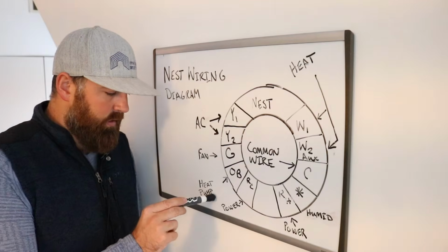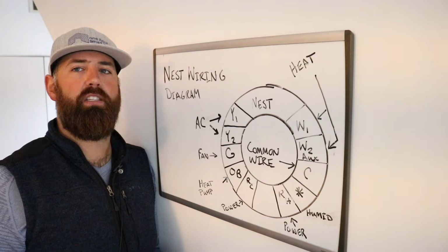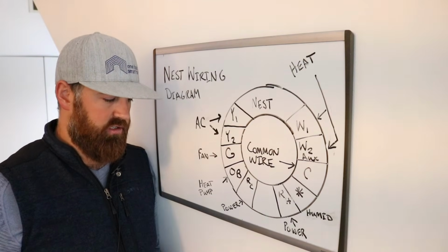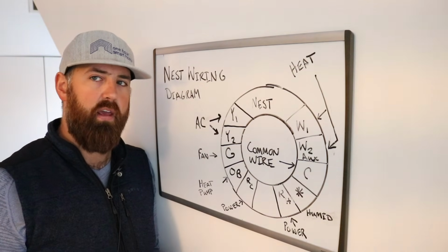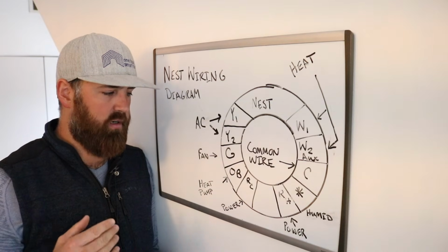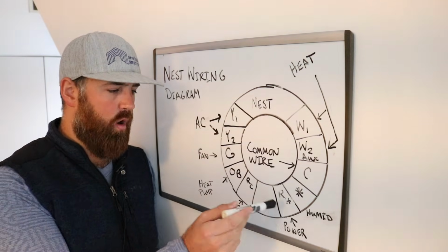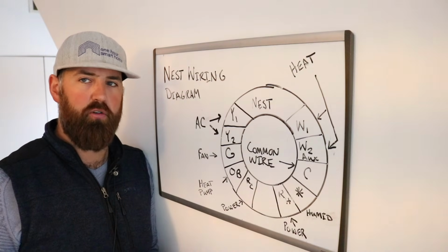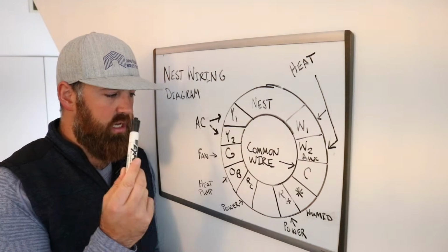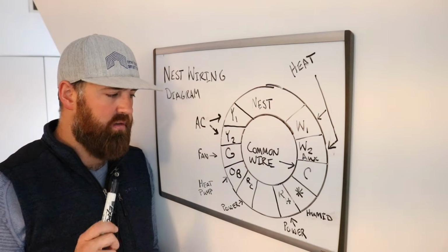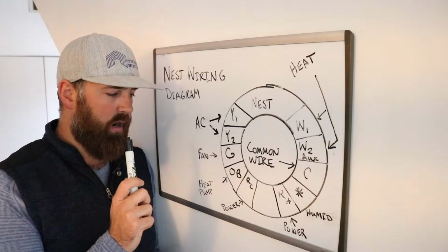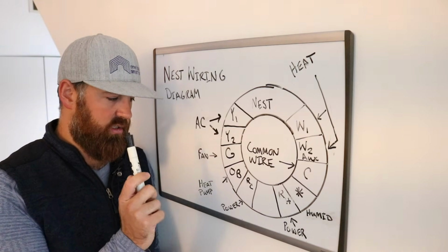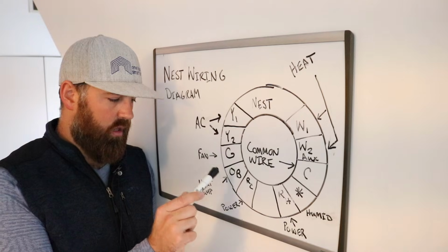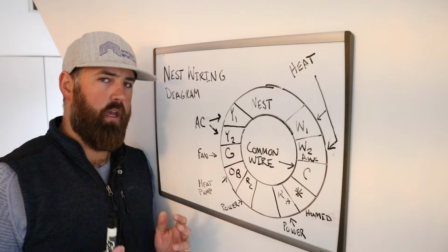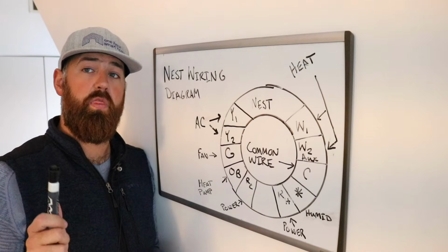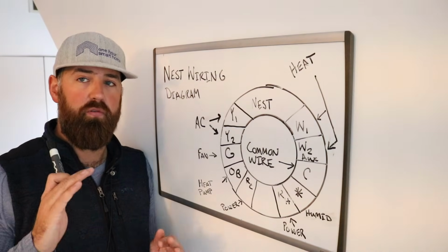The next one is the RC, and RC and RH are related - they are both power. When we talked earlier about how a thermostat and HVAC system work, RC and RH basically do the same thing for the most part in most systems. RC is power and RH is power. For most of you, you could hook up your red wire, the R wire, to either power terminal here. It doesn't matter for most people, with the exception being if you have a dual fuel system.